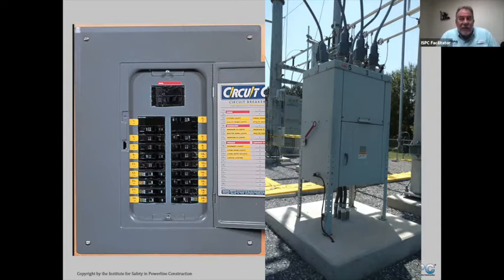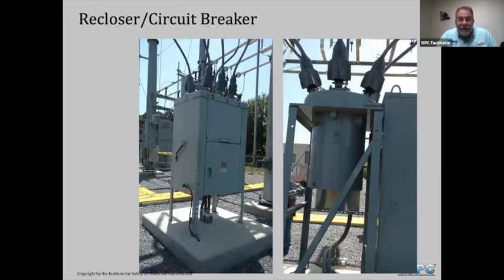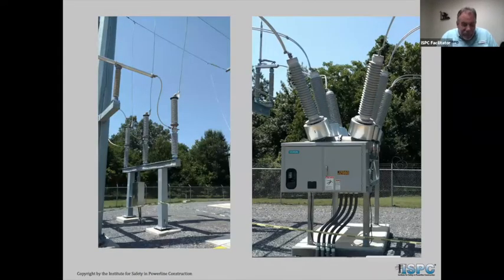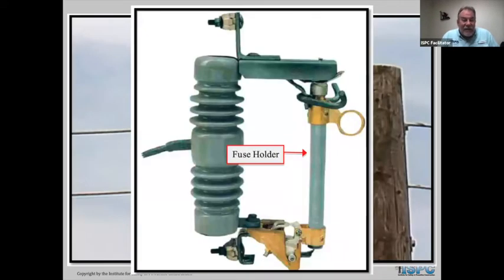So the recloser on the right, or circuit breaker, will have return current coming back towards it on the system neutral. Not that your guys would ever be in a substation working on equipment or anything like that, but I just wanted to point out the difference right there. The difference between a recloser and a circuit breaker: many circuit breakers do not reclose, they just trip the one time. Recloser, I think I've explained that well enough. So in the substation, here's just some different equipment. You can see the primary, how high it is off of the ground, some transmission breakers, the size of the insulators and things like that.